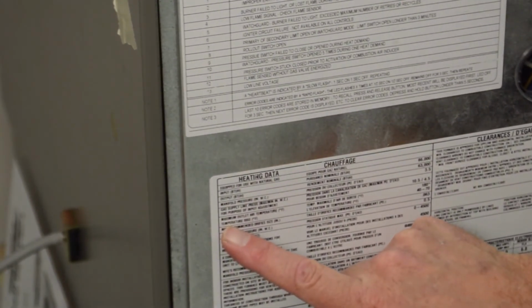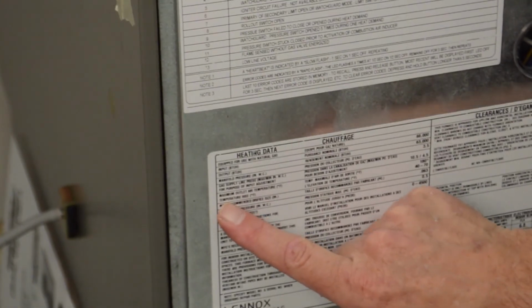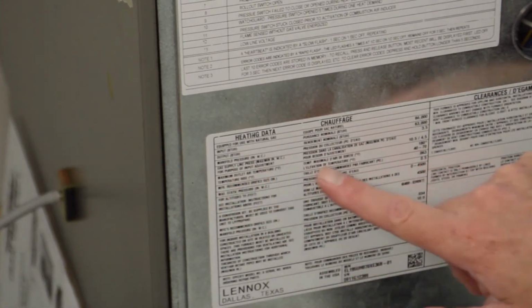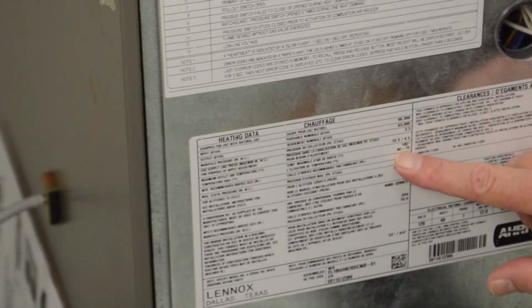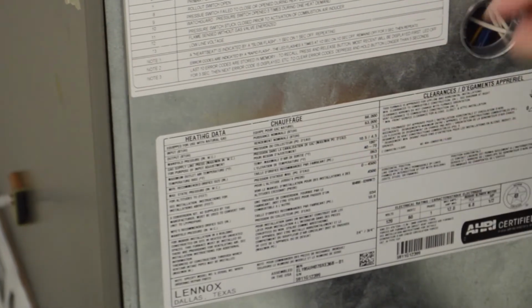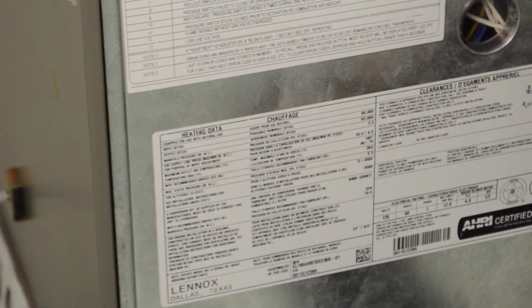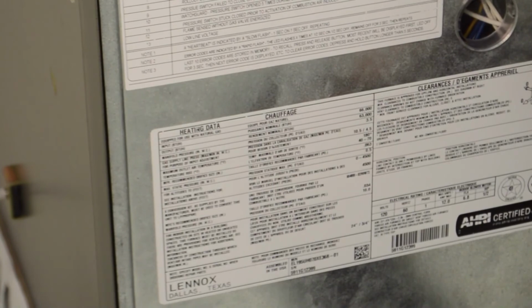Right here, the maximum outlet air temperature is 180 degrees. The temperature rise is between 40 and 70. 57.5 degrees is between 40 and 70. That is the temperature rise of our furnace.